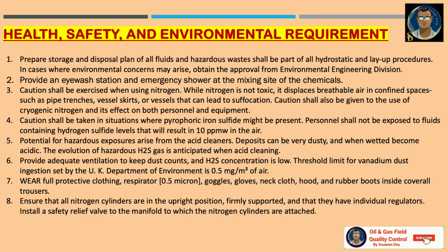Caution shall be exercised when using nitrogen. While nitrogen is not toxic, it displaces breathable air in confined spaces such as pipe trenches, vessel skirts and vessels that can lead to suffocation. Caution shall also be given to the use of cryogenic nitrogen and its effects on both personnel and equipment. Caution shall be taken in situations where pyrophoric iron sulfide might be present. Personnel shall not be exposed to fluids containing hydrogen sulfide levels that will result in 10 ppmW in the air.